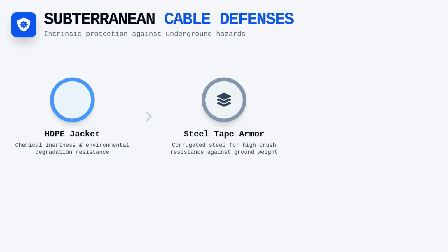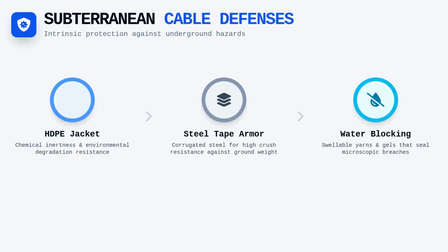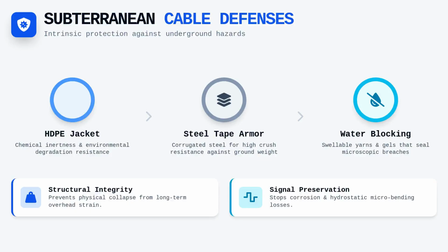To combat the pervasive threat of water, manufacturers incorporate swellable yarns and water-blocking gels within the cable structure. These materials are designed to expand upon contact with liquid, effectively sealing any microscopic breach in the jacket and preventing moisture from migrating down the length of the conduit or cable core. This is especially important for protecting metallic elements from corrosion and fiber optics from potential micro-bending losses induced by hydrostatic pressure.